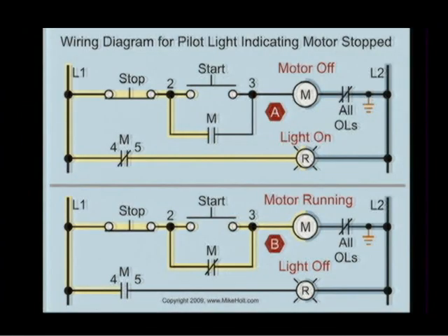All right, what do we got here? Oh, here we go. Here's that picture again. We can see voltage to the light. Red light is on. Press the start button. It closes the M contacts that were open, the auxiliary contacts, and then we had the auxiliary contacts that were closed, the 4 and 5. That'll get open. Light goes off. Indicates motor's running. We're in good shape. I love that design. That's a great one.